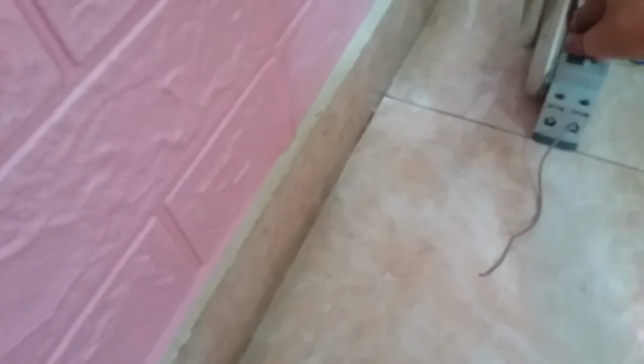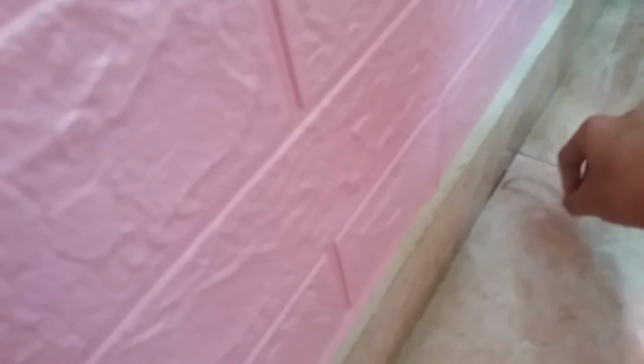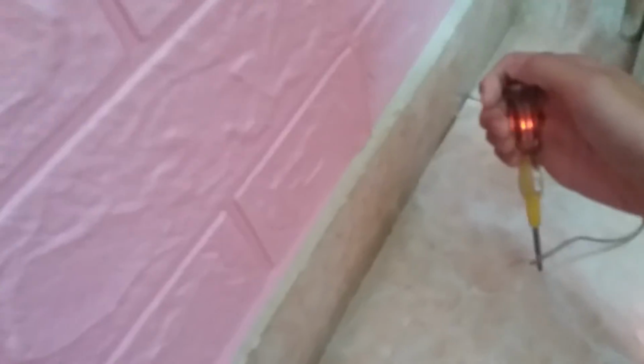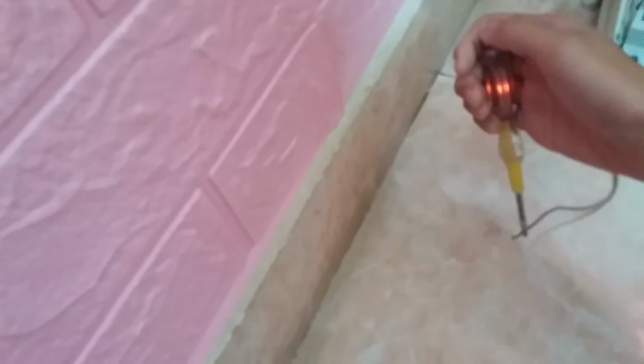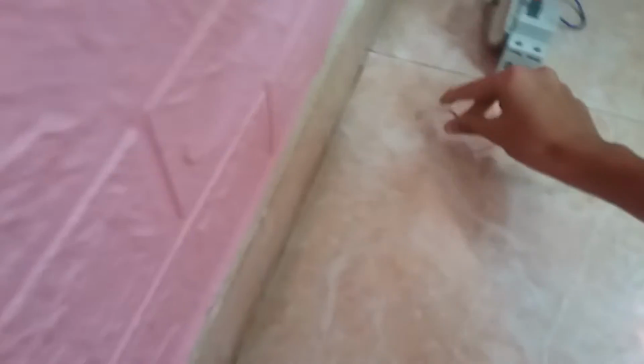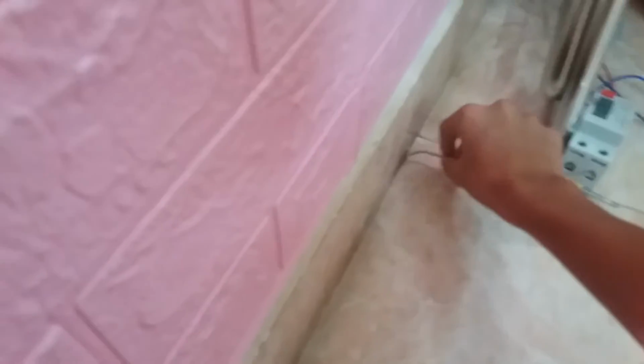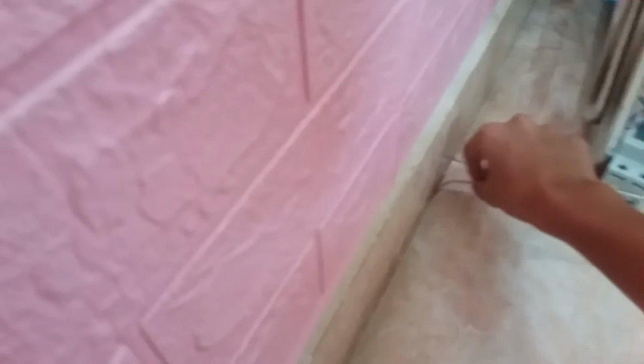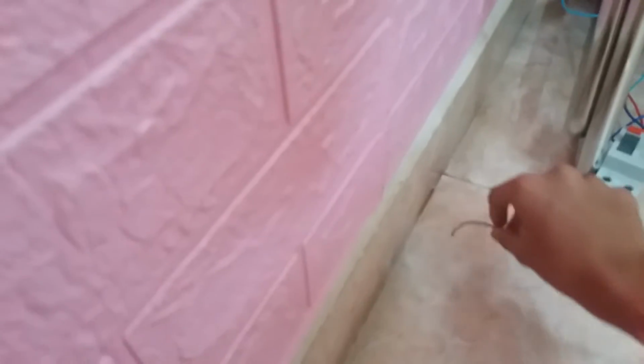And I will put some water here. You cannot test it like this because the breaker won't trip, the leakage current is not enough for the CB to trip. But with the test button it's okay.